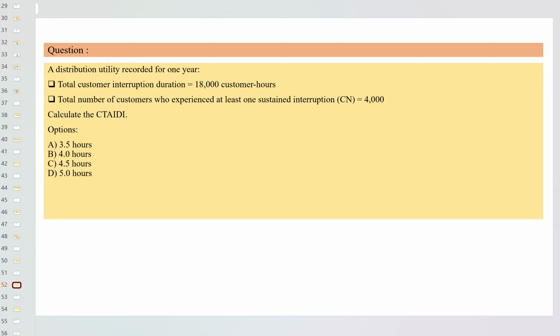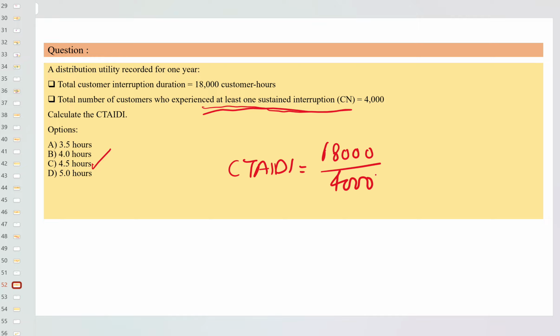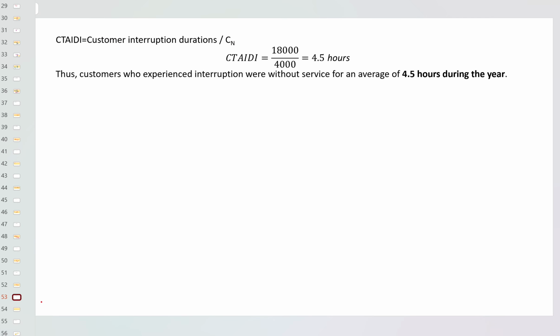Option C is correct. This is asking about a customer who experienced at least one sustained interruption, so remember, you count it at least once, not in a common zone—if a customer is affected first and then again, the intersection at least once is the common part. So CTAIDI equals 18,000 customer hours divided by the total number of customers affected in that duration, which comes out to 4.5 hours. So option C is correct, 4.5 hours.